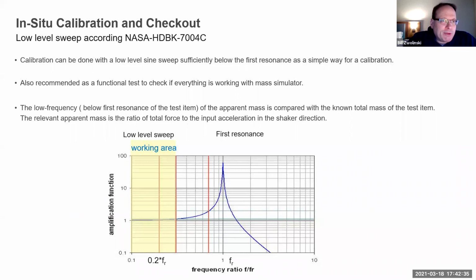So what do you do when you get everything sorted out and put together? You've got to calibrate it. The technique typically used is one where you use a low frequency sweep or a dwell below the first resonance of the vibration fixture, and you're comparing the apparent mass, force equals mass times acceleration, to the total mass. So you would have calculated the total mass acting upon the force sensors, and then by vibrating it below the first resonance, you'll get the apparent mass by measuring the force output and the acceleration output. You compare the two, and then you put in a correction factor based upon the difference.